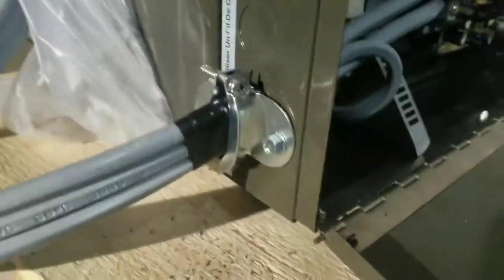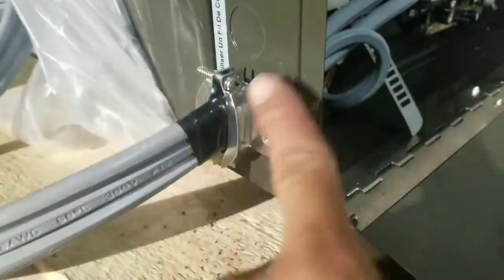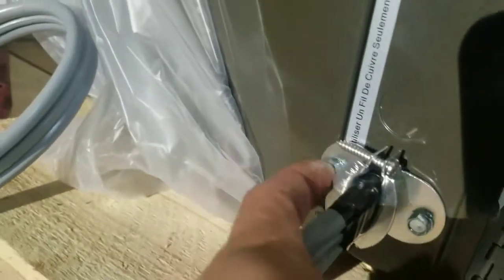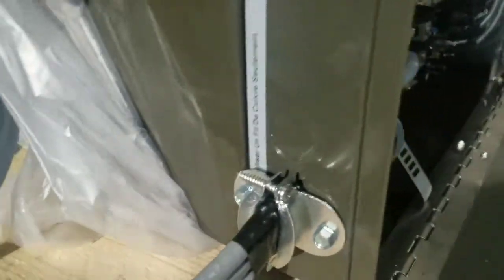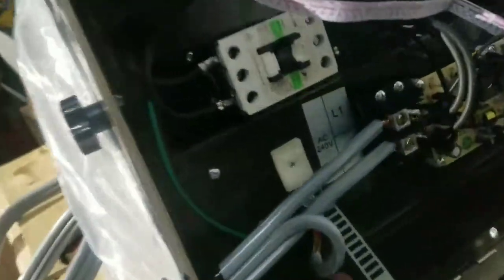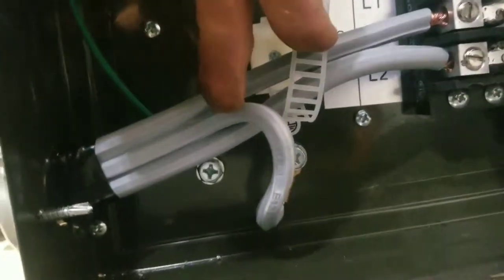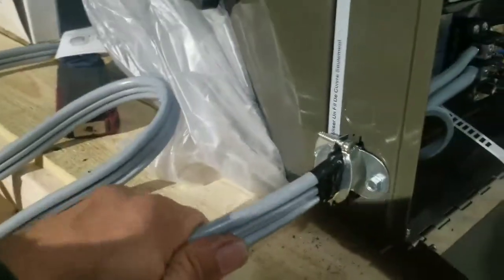Okay, so I lock it there first and then I shoot it here to lock it in place so the cable won't move. This is what I did: the white one up there I connected where it said white, so basically my white one is gonna be my ground, which is the neutral. That's the one in the center here, so I ran that to the ground, and then the two hot ones. Then I put some extra tape for extra protection, but it's not moving at all.